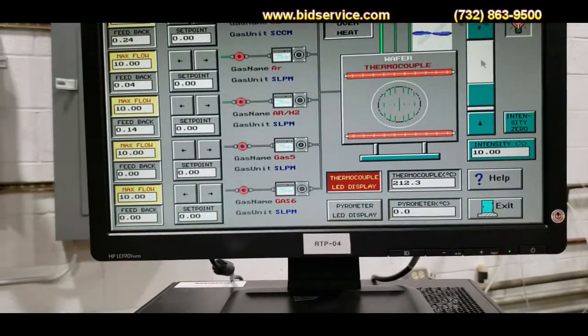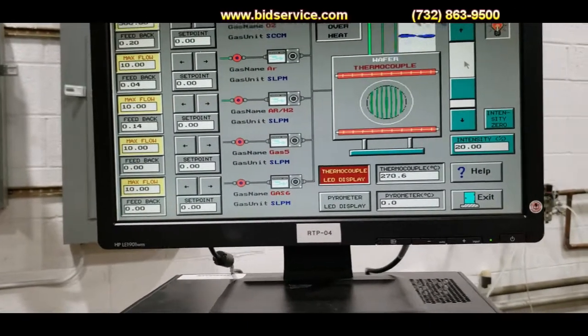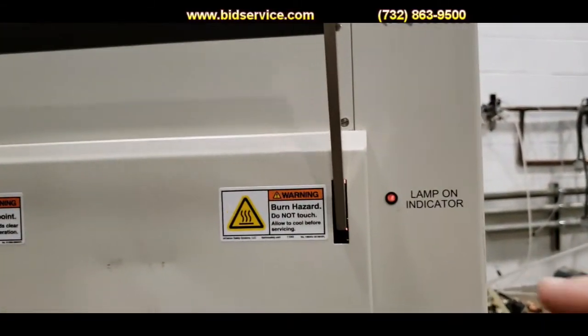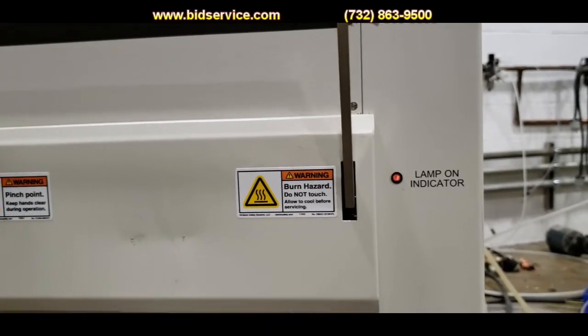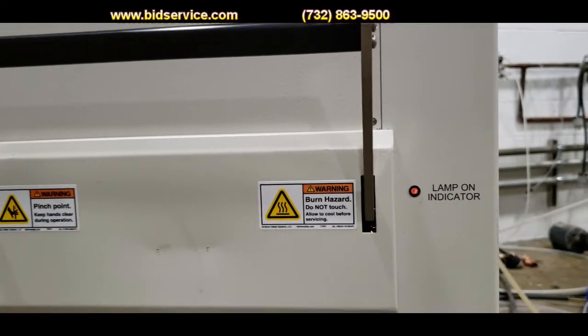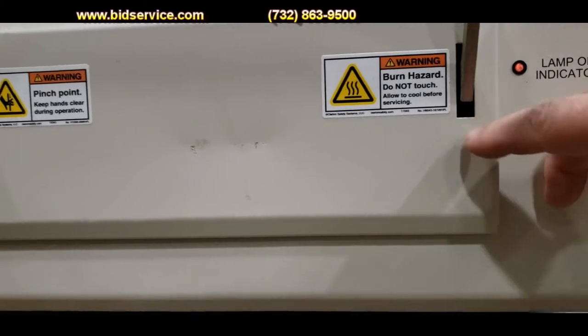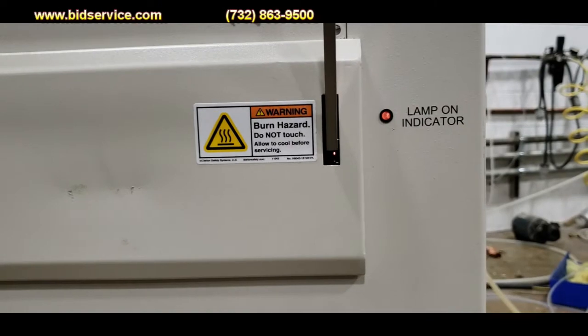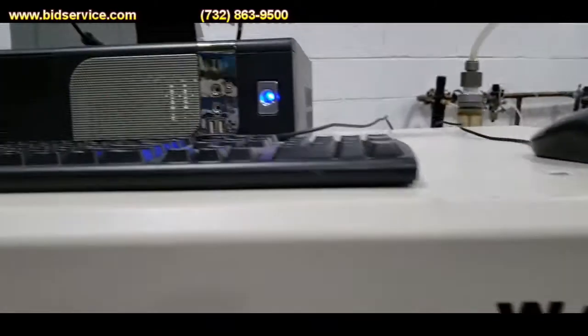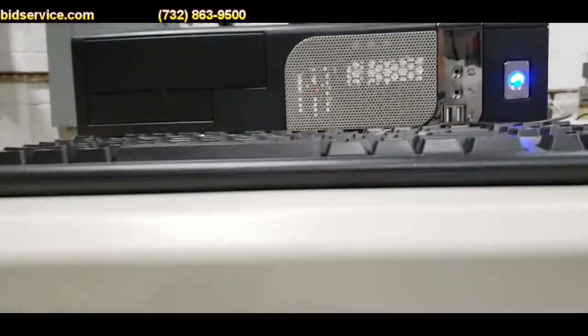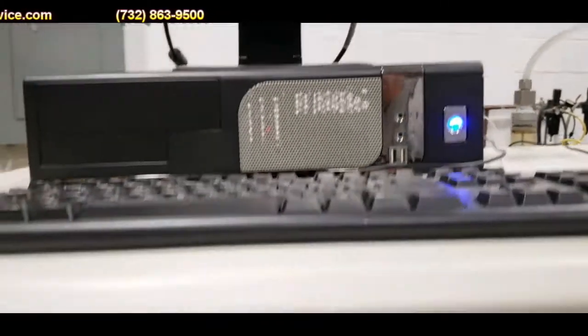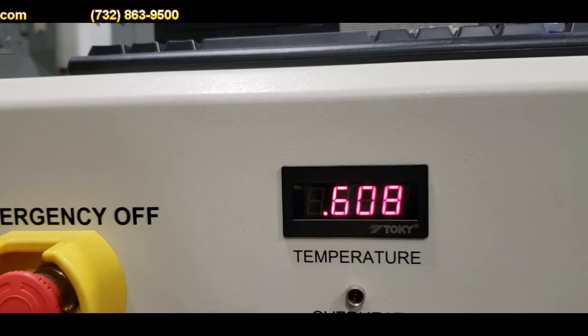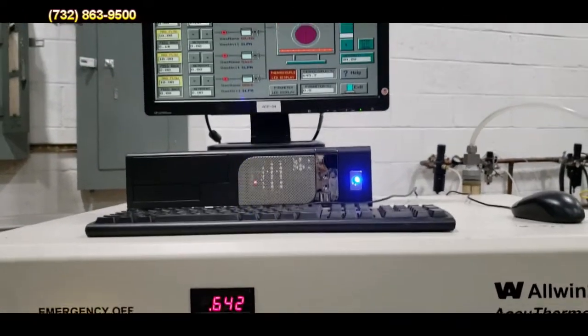I am going to ramp this up a couple more times to 20 percent. You do see once you light it up more that this indicator here does light up and show the lamps inside. That is what gives it the LED. And if you can see right in here, sometimes you can see the lamp bulbs lit up in there. So right now we are at like 520 degrees and we are still going up. You can see it is about the same thing, 585 and 590. It is still going up. We are just going to let it stabilize so you can see where it is at.